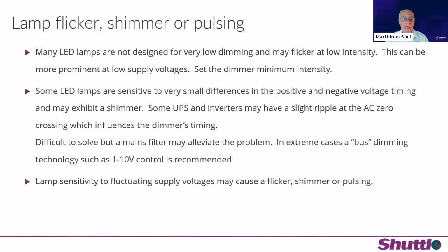The dimmer has no other way of knowing what the AC synchronization information is but to simply look at the zero crossing. So the dimmer may, in certain cases, synchronize slightly earlier and slightly later. Those differences may be as little as 0.2 milliseconds, which is really nothing. But some LED lamps are sensitive to those very small fluctuations, and you do get lamp flicker or shimmer.